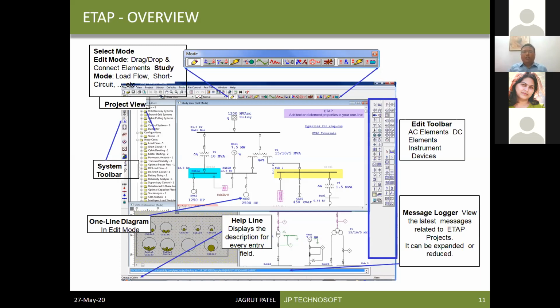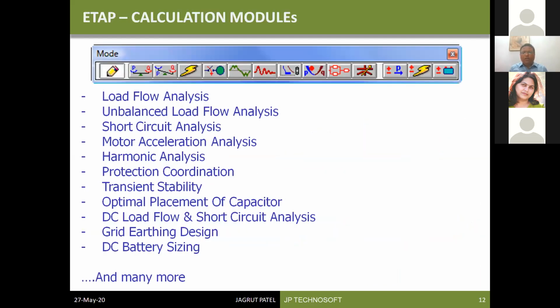So what facilities are available with ETAP software? Why are we using ETAP software? These are the tools available, the calculations which you can perform with ETAP. The first tool is load flow analysis. In power system networks, you must have studied load flow analysis: Newton-Raphson method, Gauss-Seidel method, fast decoupled method. All these methods are available in the load flow analysis calculation of ETAP. You can create a network and perform load flow analysis for either of these methods. Then there is unbalanced load flow analysis also. Short circuit analysis uses the per unit or ohmic method.